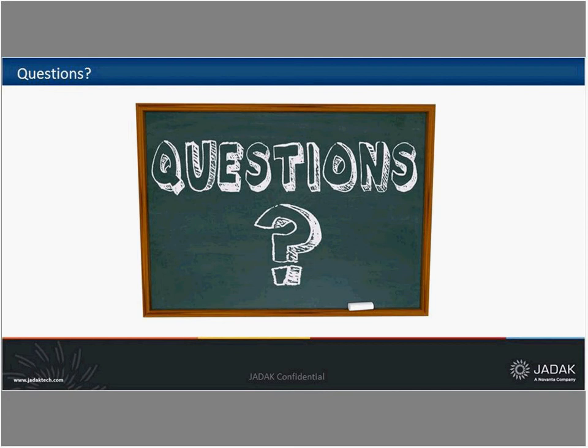Okay, great. Here's another question. The question is in regards to the special regulation for the IEC 60601 to use the NFC technology. Is there a special regulation for the IEC 60601 to use the near-field technology? No, not associated with that, because the 60601 is actually a medical directive, and anything associated with the NFC or any of the RFID interrogators is going to be more associated with radio frequency directives, whether it's the RED directive in Europe or FCC regulations in the U.S. or various other countries' regulatory agencies.